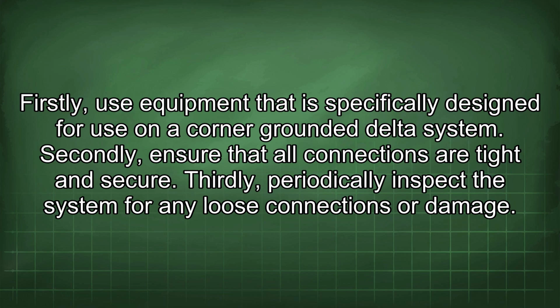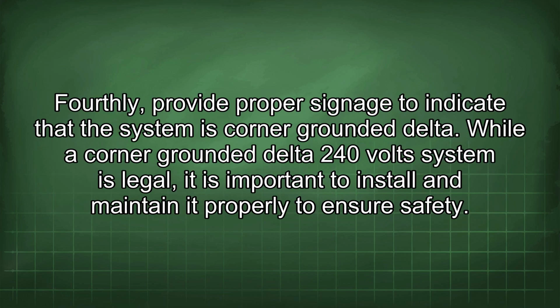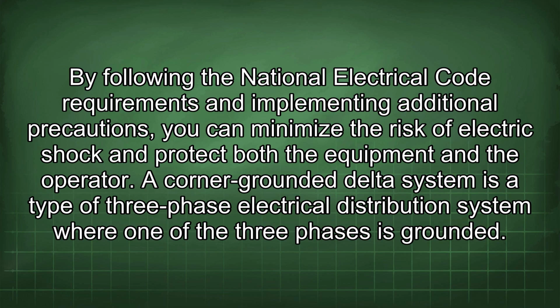Firstly, use equipment that is specifically designed for use on a corner-grounded delta system. Secondly, ensure that all connections are tight and secure. Thirdly, periodically inspect the system for any loose connections or damage. Fourthly, provide proper signage to indicate that the system is corner-grounded delta. While a corner-grounded delta 240-volt system is legal, it is important to install and maintain it properly to ensure safety. By following the National Electrical Code requirements and implementing additional precautions, you can minimize the risk of electric shock and protect both the equipment and the operator.